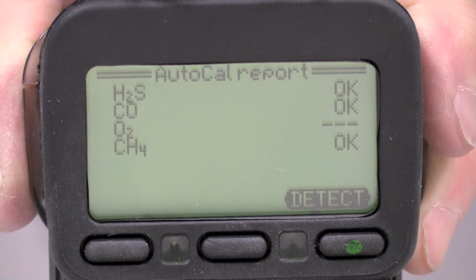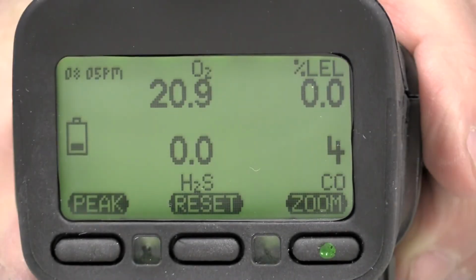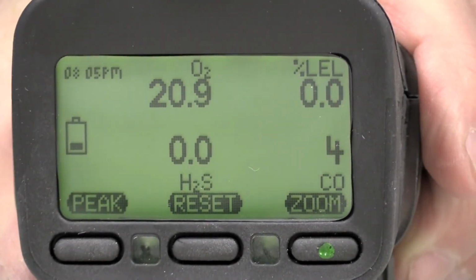Since the sensor is not adjusted, the report screen shows dashes instead of an OK message. Make sure that the LEL, CO, and H2S sensors show an OK message. Press Detect to return to normal operation. The instrument is now ready for use.